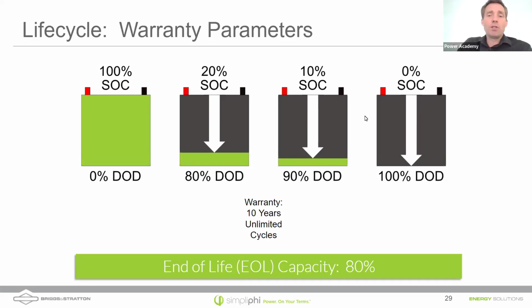We have different recommendations depending on how often you're cycling a battery. If you're cycling it every day as an off-grid customer, we recommend an 80% depth of discharge. If you're only cycling it occasionally, 90% or even 100% depth of discharge is fine, because at 10,000 cycles, once a day, you're looking at 26 years. At 6,000 cycles, you're still looking at 18 to 20 years. A long time. But it depends on the environment, and you won't always discharge them the way we do in the lab.